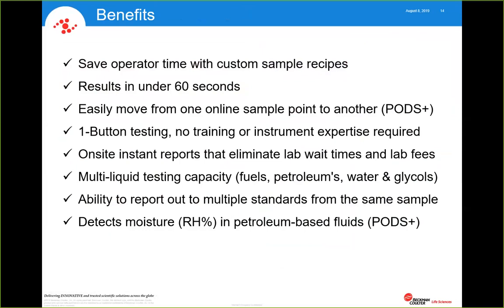Let's see. Multi-liquid testing capabilities. So this is kind of new especially for the PODS Plus, not so much for the 811 Plus, but it's fuels compatible. We can test things all the way down to waters, glycols, and of course the petroleum-based fluids, all the way up to and including 425 centistokes at ambient. Again, we're able to report out to multiple standards from the same sample.